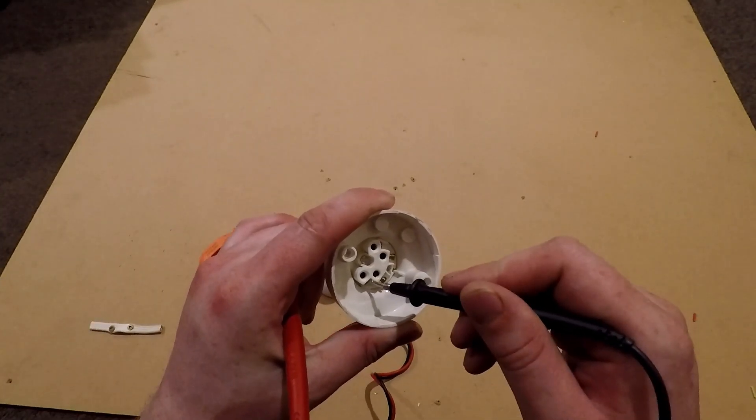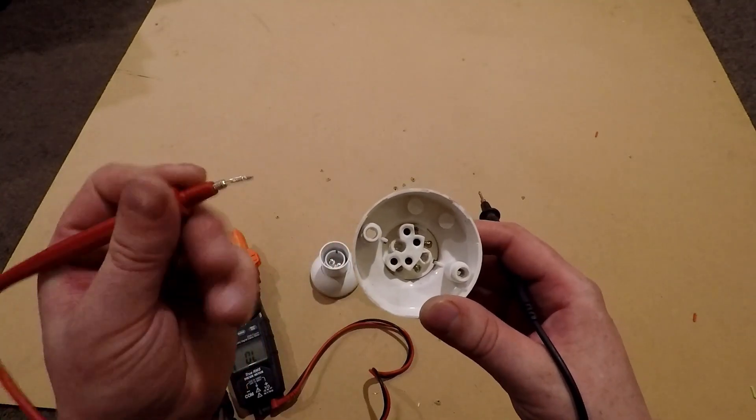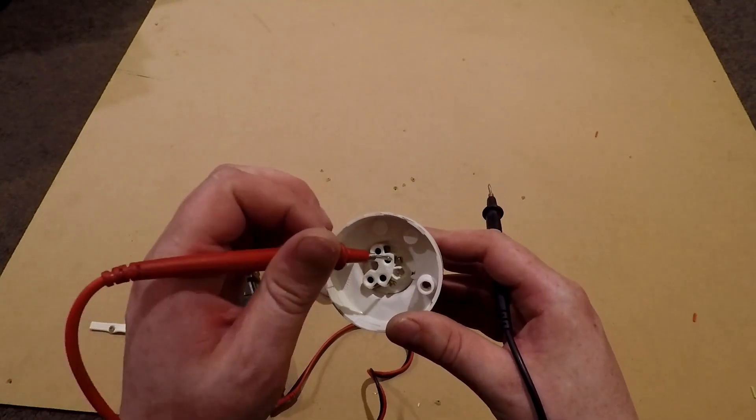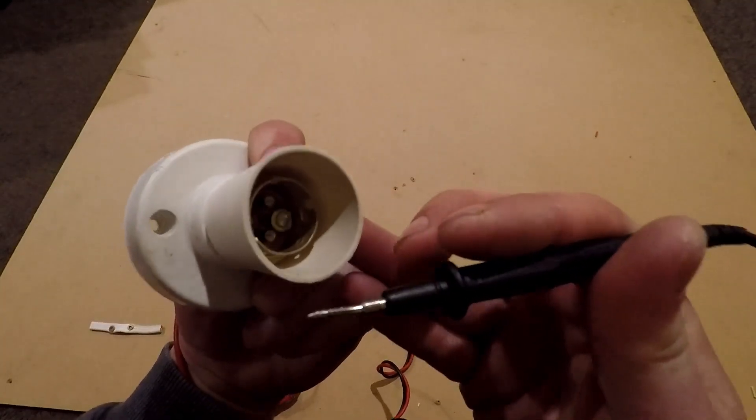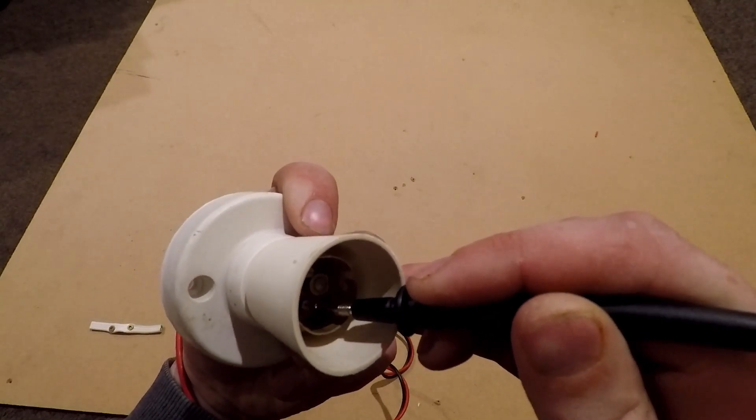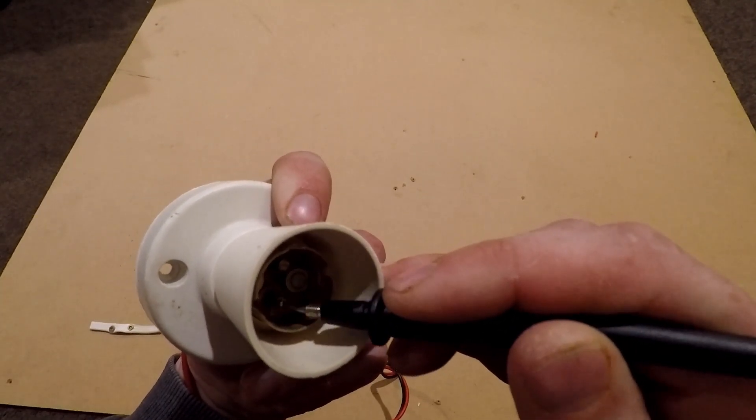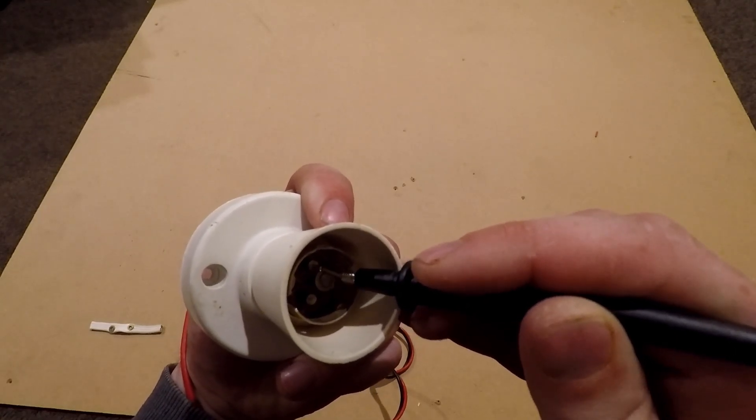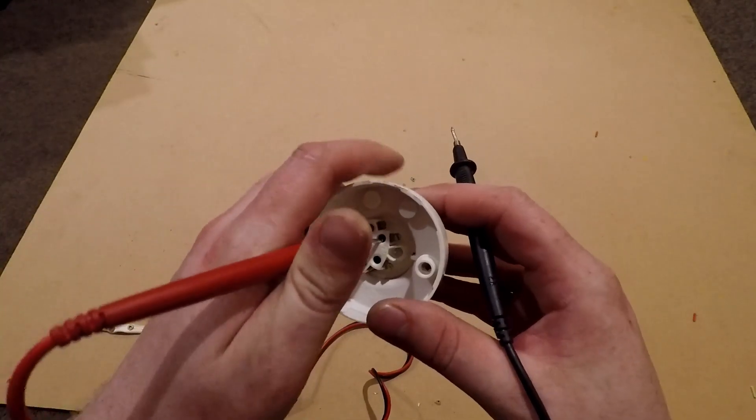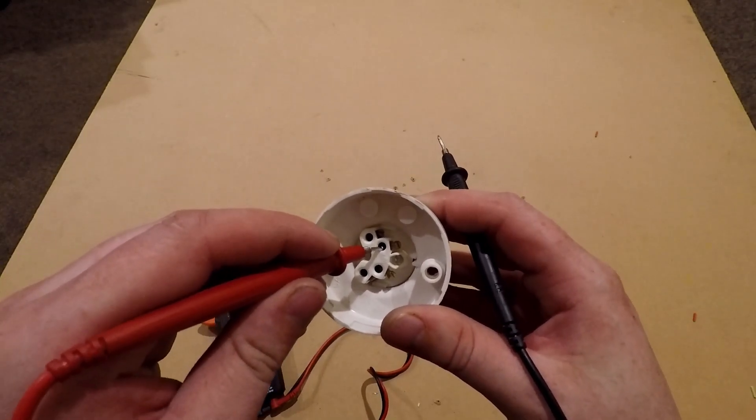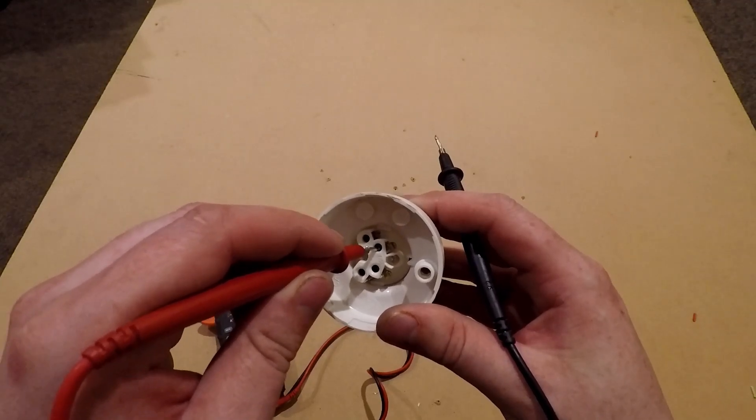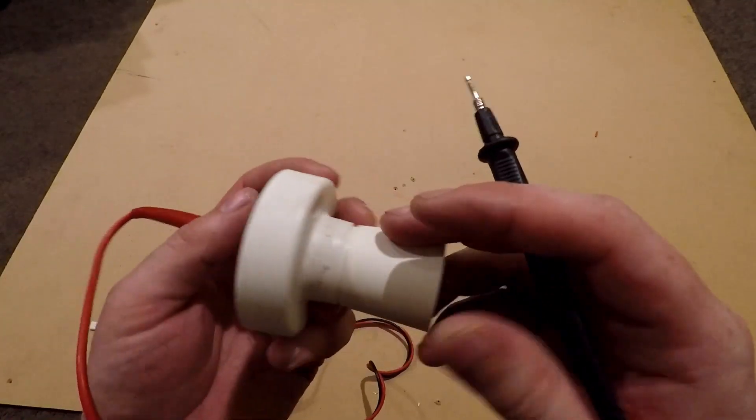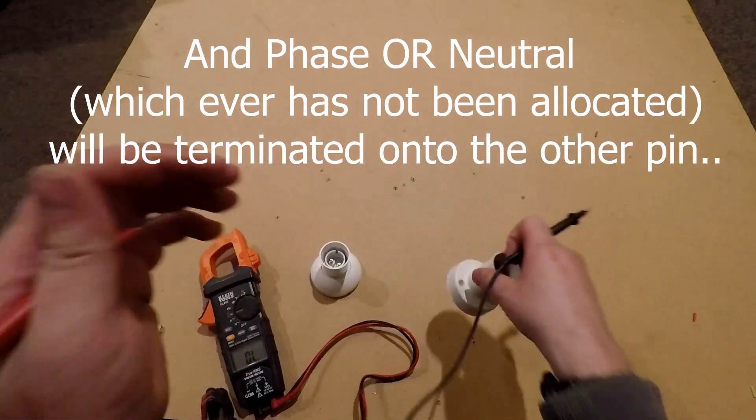Now we'll try these two front ones. So put one end on that terminal and we'll test these pins with the other end. So no continuity on that one, and there we go, that pin there corresponds with that terminal there. So we're going to want to put our phase or neutral cable into that terminal. Now we'll try this terminal, there we go, so we know that that's that pin.